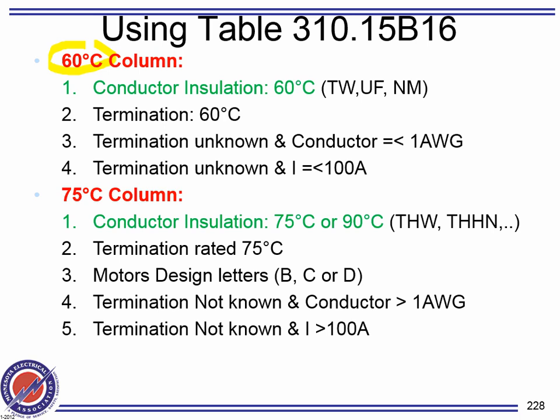Number 1, if the conductor insulation says 60. You guys hear me? If you have TW, UF, do you even have a chance? 60. You're doomed. If the terminal says 60, if they tell you the termination lugs on the piece of equipment are rated for 60, you're doomed, regardless of what your installation is. If you have no idea what the installation is, and the conductor is number 1 or less, yeah, they don't tell you what the installation is, but the conductor coming to the piece of equipment is 1 or less, then you must use 60.